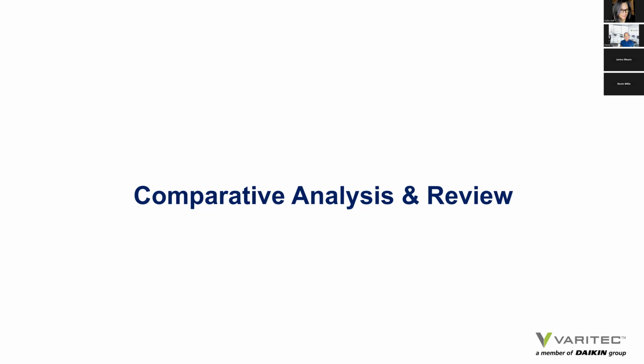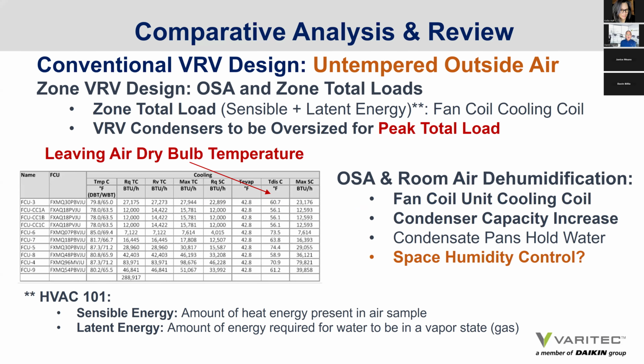Let's look at this actual performance review of the three design scenarios, and let's go through them quickly. Well, if we look at the variable refrigerant fan coil selections with untempered outside air, what's rather interesting, the discharge temperature off the cooling coil at the fan coils local to each zone isn't even at 55. It's very hard during a monsoon design day to hit actual condensation, not to say that you're not having condensation form. It's a question of whether or not you're adequately controlling humidity in the space. And by the way, when your condensate pans fill with water, that exposed water in a building is contributing to the humidity effect. Just be aware of that.